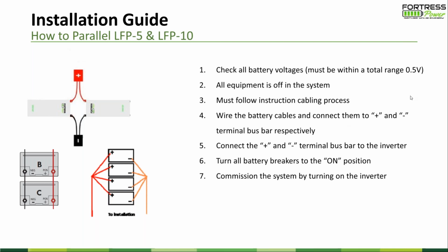Not good. So if you want to do DC chain, as I show in the picture on the left, there's a B and C battery, then you want to make sure you pull the power from both sides. And the other way we recommend is we use the same length wiring system. So if that's like eFlex or eVolt, we allow the customer to stack up 15 or 20, 40. Then we always want the batteries to have the same length of battery cable and go on the bus bar and go to the inverter. It's easy for installation and also keeps the balance of charge and discharge of the battery system.